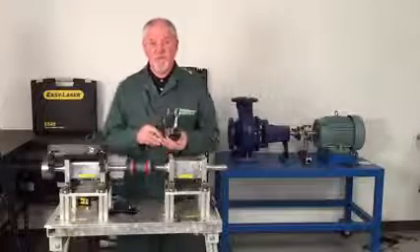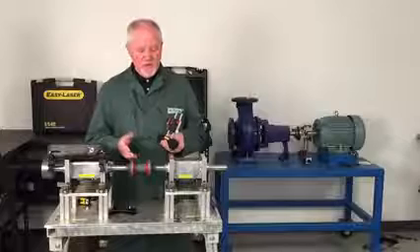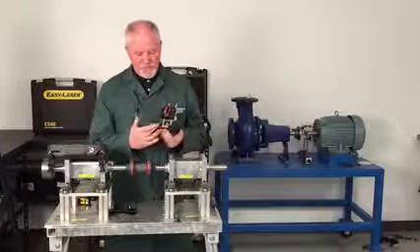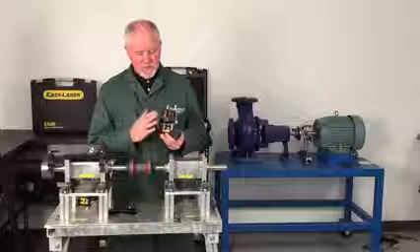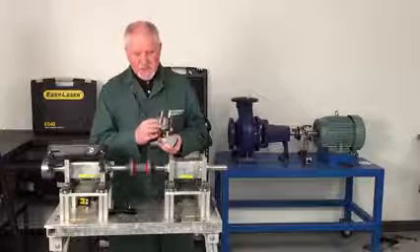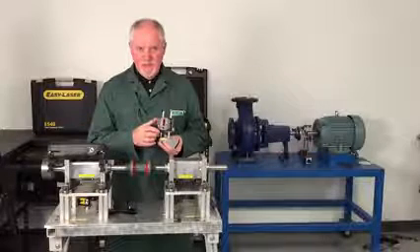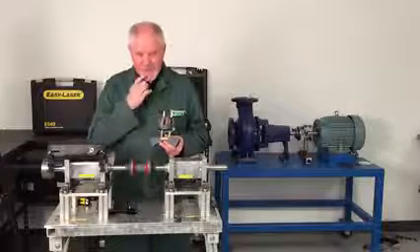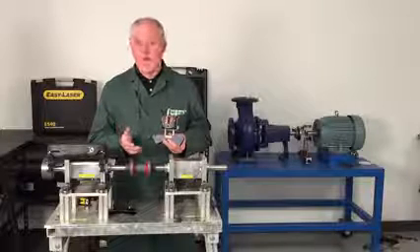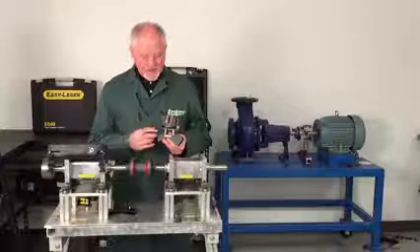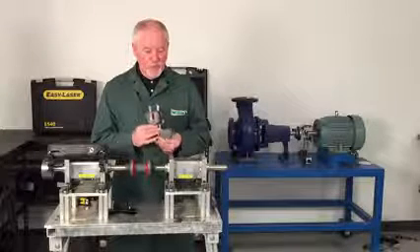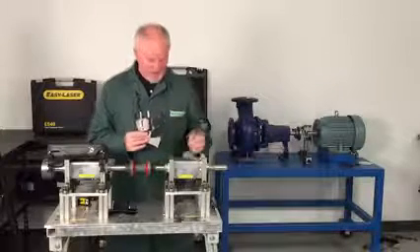I'm going to show you the simplicity of use, but first of all, let me just show you when you actually take the detector out of the box, it comes pre-mounted on a bracket. This is the detector. It has a beam that comes out of here, and this is the detector slot. It's 30 millimeters in length, so that's almost an inch and a quarter. That's a huge amount of travel. So rough alignment is easily done on this. You can actually see this one's got an M on it, which is for the movable machine, which we choose to be this side.